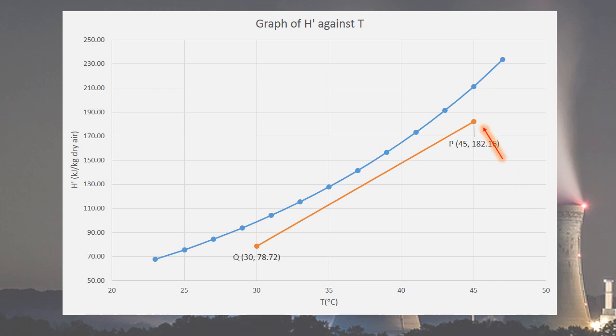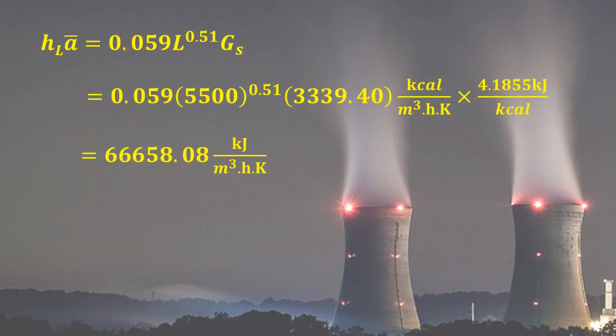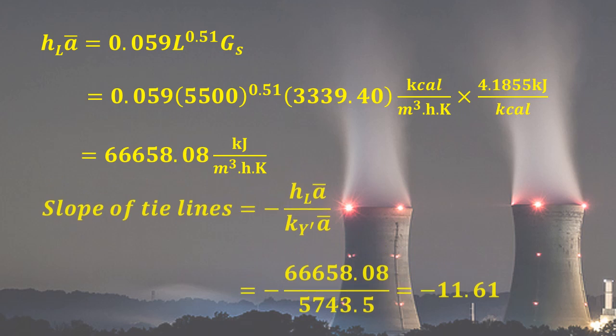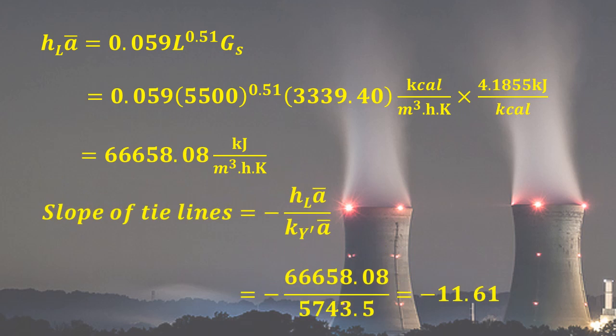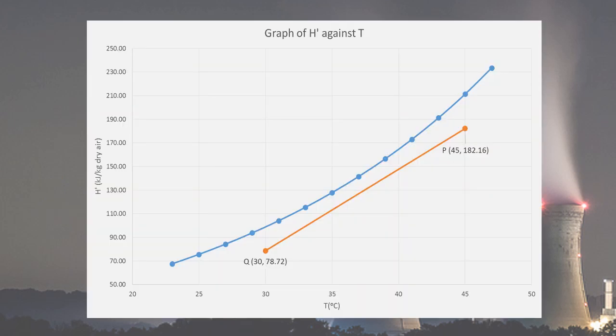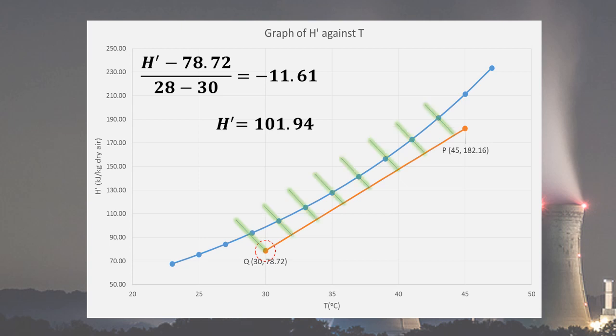Then, to construct a tie line, two points are needed: one at point Q, while the other is obtained by calculating H prime at temperature 28 degrees Celsius. This tie line must intercept the equilibrium line at point TLI and HI. More tie lines are then drawn parallel to each other.